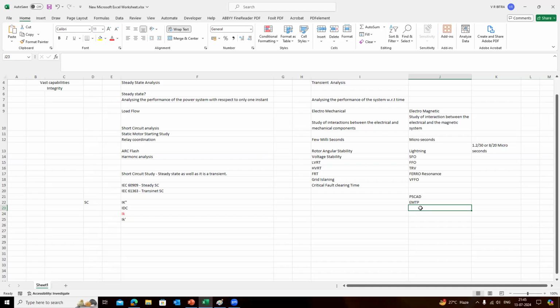Say for example, for a 400 kV equipment, the continuous current is 3140 amperes. This has to be validated by load flow. You may be saying 50 kiloamperes for 1 second. This can be validated using the short circuit, right? In addition to that, you may have something like 1425 kV, which is basically the BIL, meaning the basic insulation level. In order to validate this, you need to perform these studies. Whether you are looking at increasing the surge arresters or identifying the right characteristics, or you are increasing the BIL value of each and every equipment, that has to be studied as a part of the EMT study.